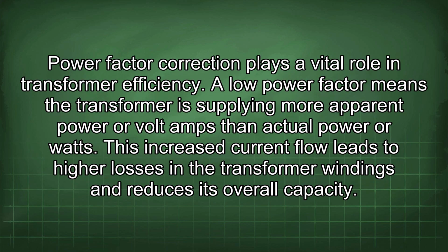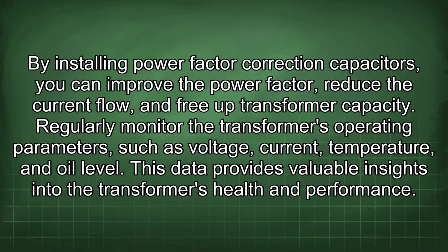Power factor correction plays a vital role in transformer efficiency. A low power factor means the transformer is supplying more apparent power, or voltamps, than actual power, or watts. This increased current flow leads to higher losses in the transformer windings and reduces its overall capacity. By installing power factor correction capacitors, you can improve the power factor, reduce the current flow, and free up transformer capacity.